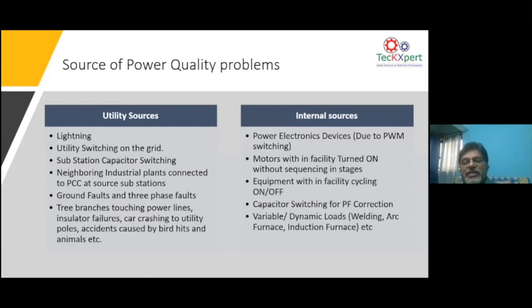And when it comes to load related causes, the consumers who are connected to the TNEB grid have a lot of power electronic loads like drives, VFDs, and lighting loads. Sometimes when consumers switch on large motors, that can create a voltage fluctuation in the grid. Sometimes people use dynamic loads like welding and arc furnaces, which again can cause fluctuations on the grid. So ultimately, the utility, the consumer and the manufacturer, the three have to coordinate with each other to ensure the power quality problems are minimized.